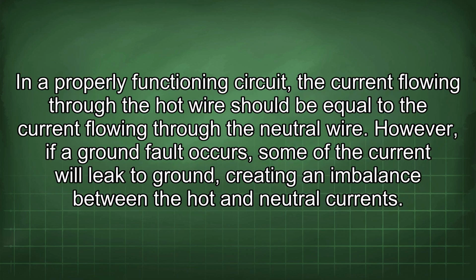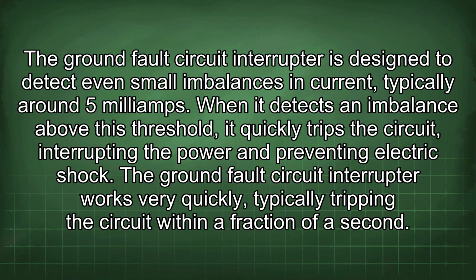In a properly functioning circuit, the current flowing through the hot wire should be equal to the current flowing through the neutral wire. However, if a ground fault occurs, some of the current will leak to ground, creating an imbalance between the hot and neutral currents. The ground fault circuit interrupter is designed to detect even small imbalances in current, typically around 5 milliamps. When it detects an imbalance above this threshold, it quickly trips the circuit, interrupting the power and preventing electric shock.